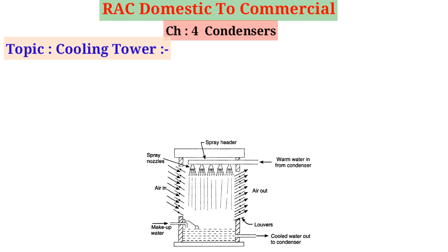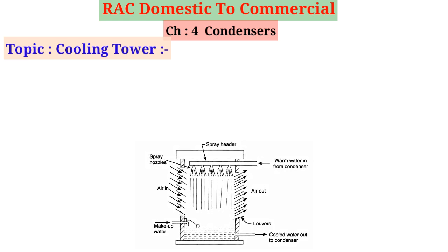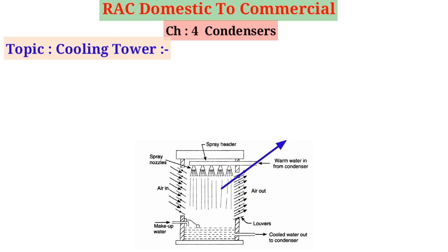Simply, the cooling tower is the system that accomplishes this process. It transfers heat from the condenser water to the atmospheric air. Most of the heat transfer is accomplished by the evaporation of a small percentage of the condensing water into the atmosphere. The heat required for evaporation is taken from the bulk of condenser water, thus cooling it.